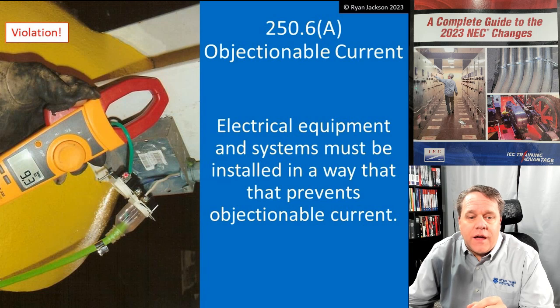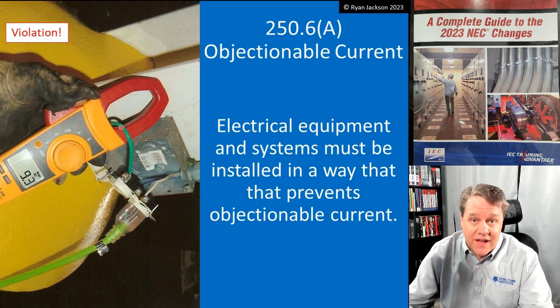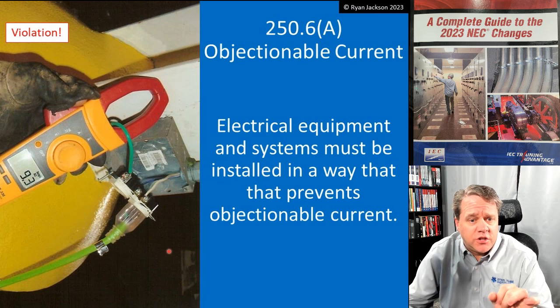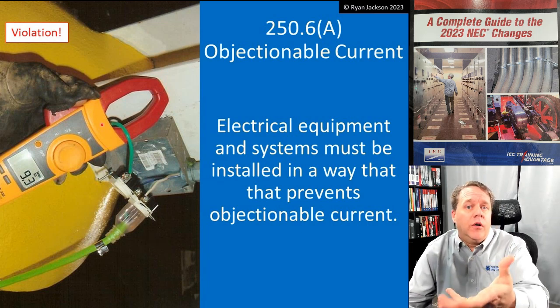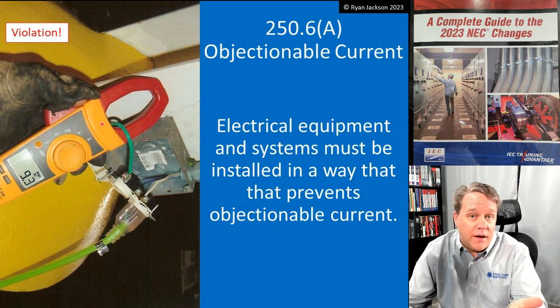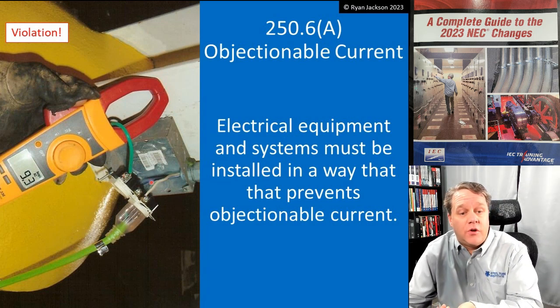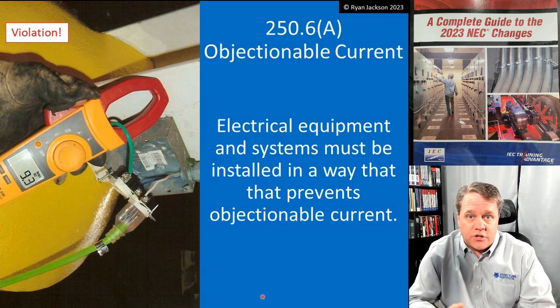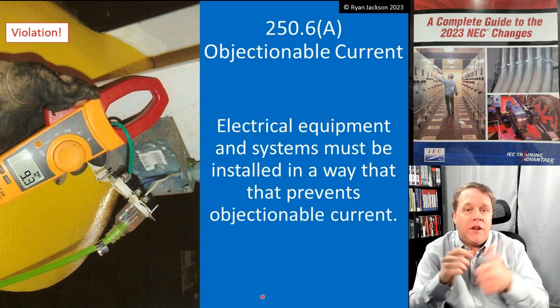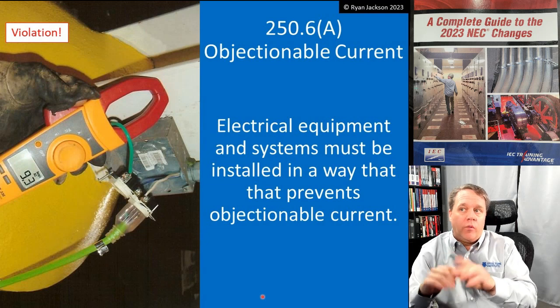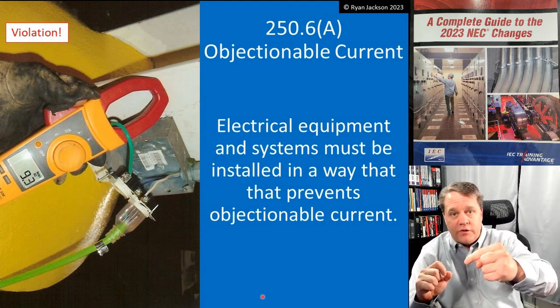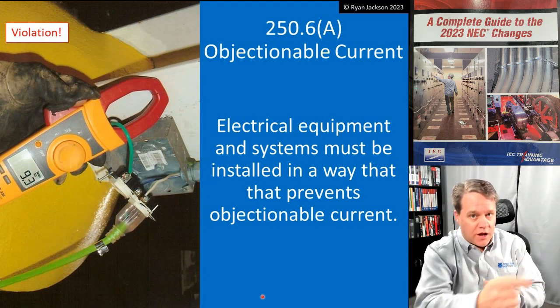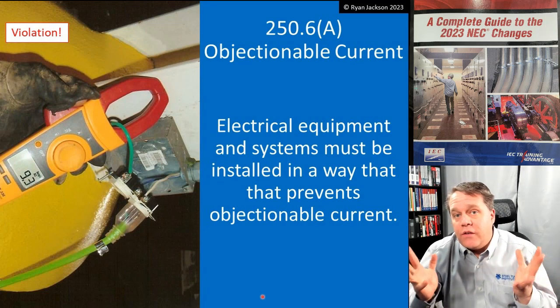Here you have nine and a half amps on the equipment grounding conductor — that is objectionable current, no question. The other photographs from this installation show 19 amps on the hot conductor, 10 amps on the neutral, and 9 amps on the equipment ground — absolutely a code violation. Why would you have 19 amps on the black, 10 on the white, 9 on the equipment ground? Kirchhoff's law says the amount of current leaving the power supply and the amount returning are always the same.